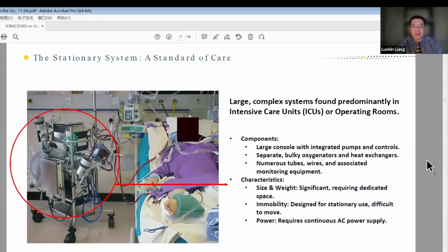When we talk about ECMO, in our mind we are always thinking about the ICU, beside the patient's bed, there's a large complex system, predominantly in the ICU or operating room. They have a large console with an integrated pump and controls. They also have a bulky oxygenator, and most of the time a separate heat exchanger. They have numerous tubing and wires and associated monitoring equipment around the patient. The size and the weight are significant. Usually they require a dedicated space to put that system. And this system is designed for stationary use, so it cannot move around, and it also needs a continuous AC power supply to power the system.